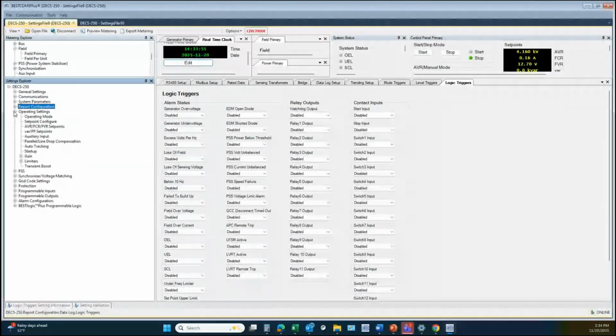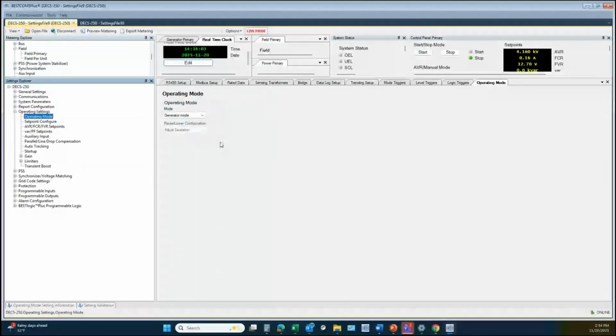But to continue on, we're going to go to operating settings, and then within the operating settings, the DECS 250 can be used on generators or synchronous motors. And so we have that option there. Set point configure will be where you typically enable the autosave. So as you make set point raise and lowers, it will automatically save that as a new set point value.